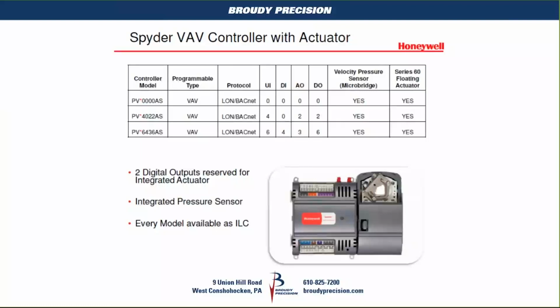Goes in quick. Now the next in line there is the 4022AS. So that's got 4 universal inputs, 2 digital outs, and 2 analog outs. That works great if you have an electric reheat, or even if you have an SCR reheat. You have your 4 universal inputs, so you could use Sylk or a conventional wall module. You could use discharge air sensors. Whenever you have a heating coil, I always recommend having a leaving air sensor. So that particular controller would work out really well.